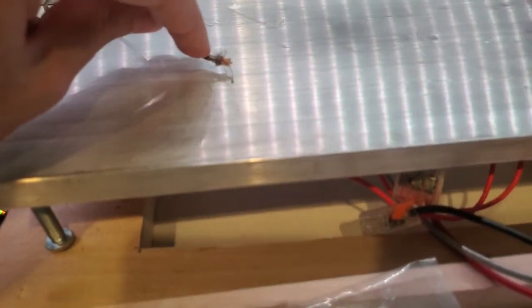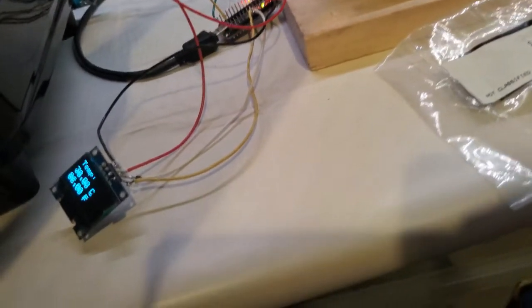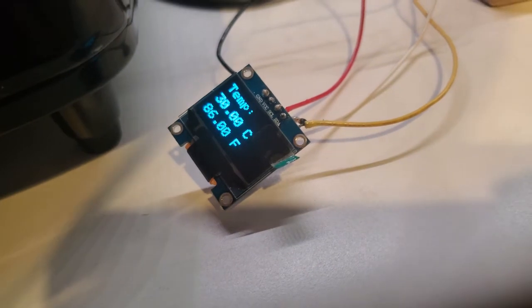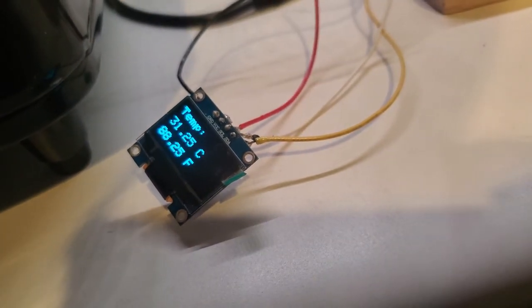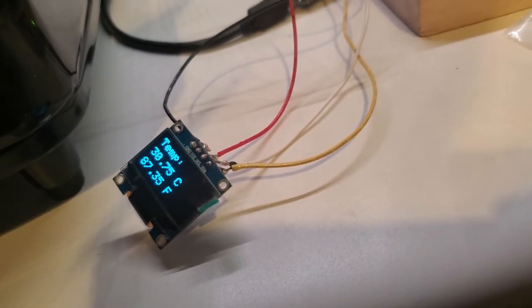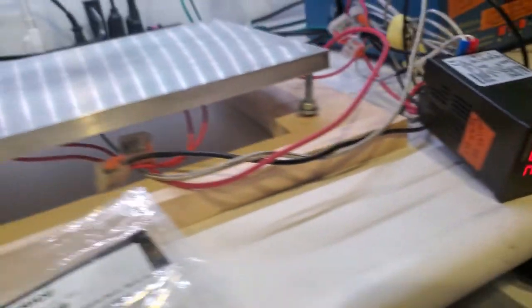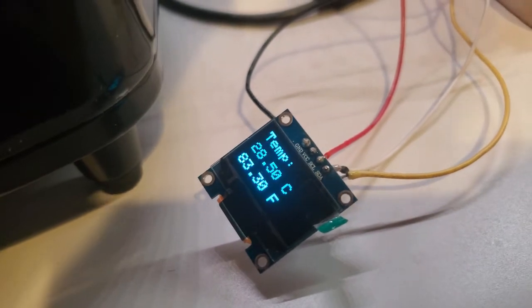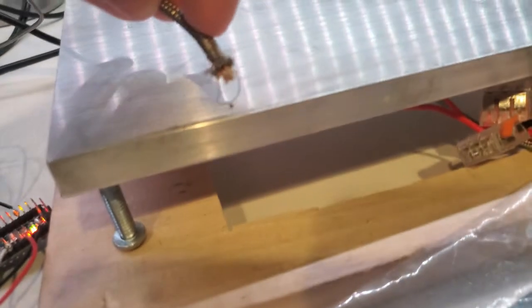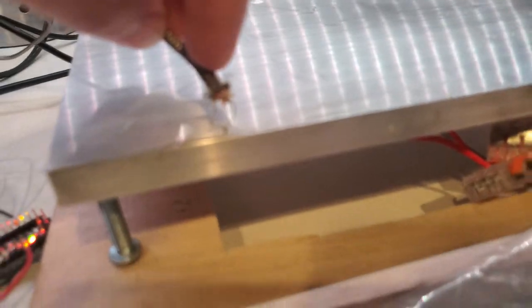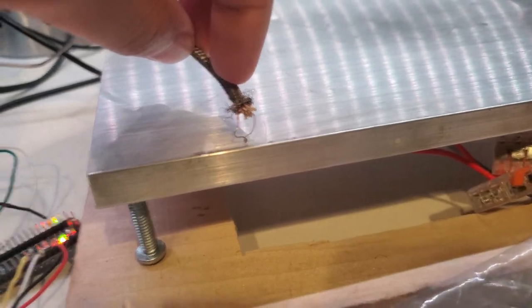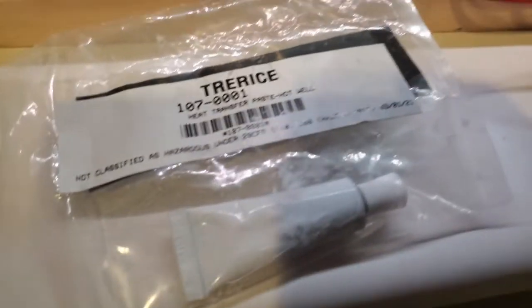If I just touch the probe to the surface of the hot plate, it'll tell me what the temperature is, and it'll just read that as, say, like 32 degrees Celsius or something like that—31. But then this says it's 40 degrees Celsius. So which is right? It's important to know when you're measuring the surface of something, you don't have very good surface contact with the thermocouple—the actual junction there—so you don't get a very good heat transfer from the surface to that thermocouple.